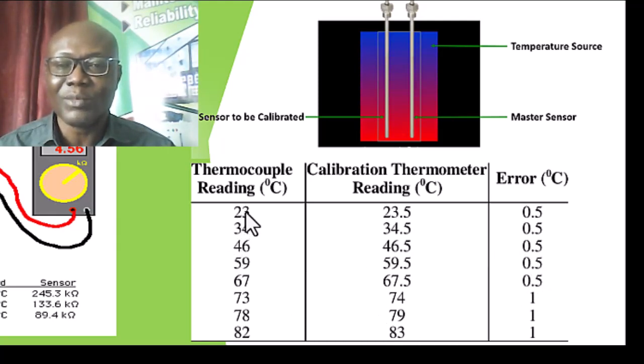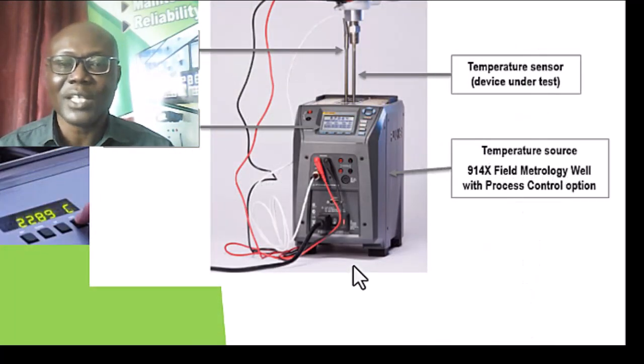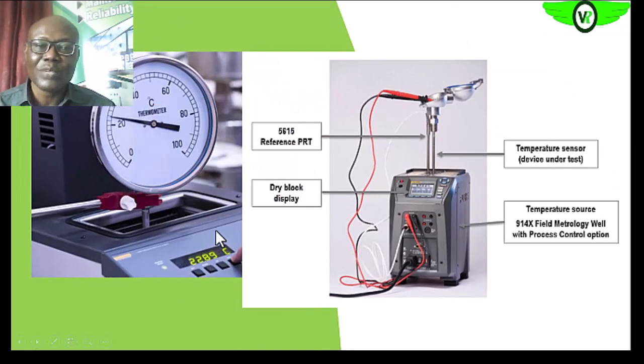Okay, so you see when the thermocouple is 23, the calibration thermometer reading is 23.5. Are we getting it? So they are very close together, which means that it is acceptable. So here is a heating bath that we can use for calibration. Here we can increase the temperature of the heating bath. We drop the instrument, that is the temperature gauge, with the sensor into the bath, or the calibrator, and then we look at the temperature reading, which is the standard. This now becomes our master meter, which is 22.89 degrees Celsius.